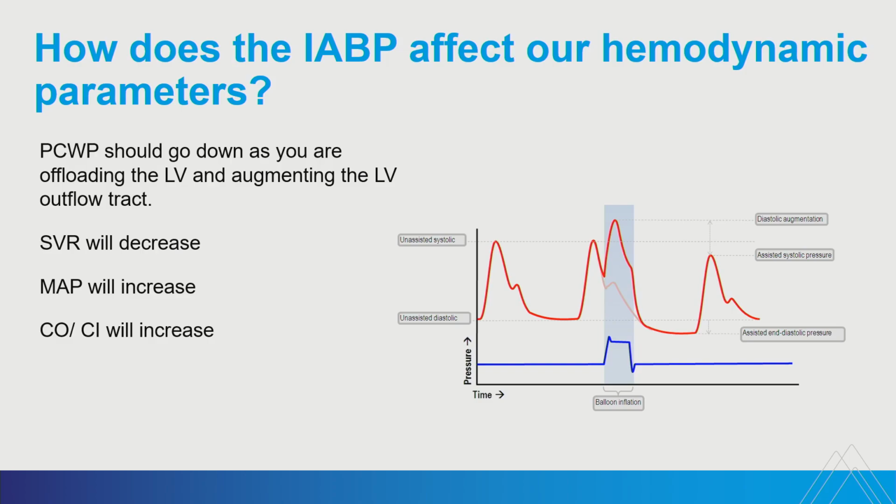So it's not going to compete, but it's going to give you a little more support for the mean arterial pressure during AFib if you can be ECG trigger. If you can't, it's going to be a pressure trigger, and it's going to be conservative. It's going to try to drop. So keep your pump in auto whenever possible.